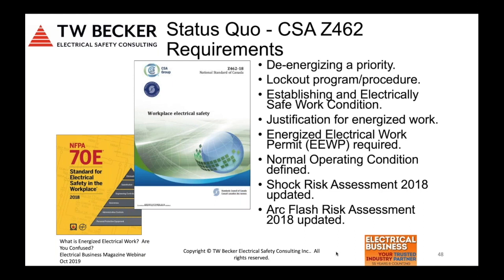Again, de-energizing is a priority. A lockout program procedure should be in place. Establishing an electrically safe work condition is a key concept in 70E and Z462, and I still think that key concept isn't used effectively as a procedure. And again, training is provided to the qualified electrical worker. They get these concepts trained to them, but if you don't have the electrical safety program with the policies and practices, then they won't necessarily follow up and actually use the training when they are doing energized electrical work.